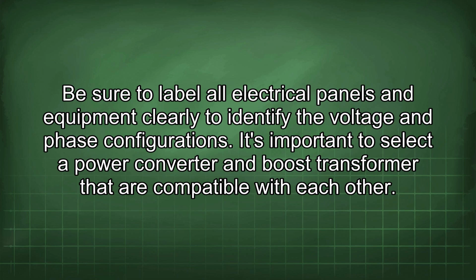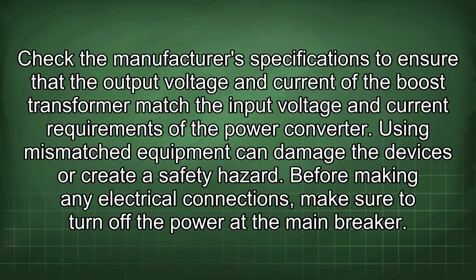It's important to select a power converter and boost transformer that are compatible with each other. Check the manufacturer's specifications to ensure that the output voltage and current of the boost transformer match the input voltage and current requirements of the power converter. Using mismatched equipment can damage the devices or create a safety hazard.